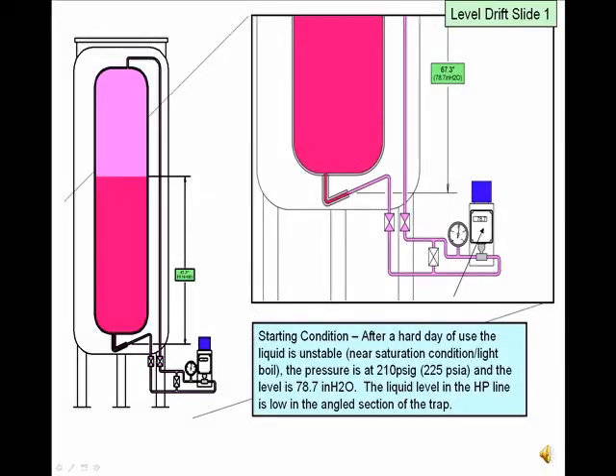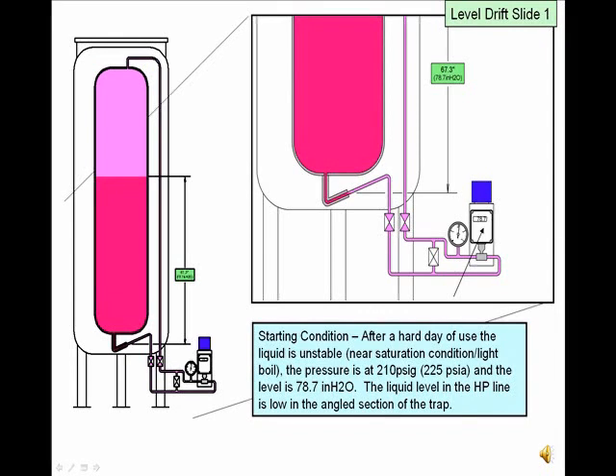For the following example, the tank has seen heavy use during the day and is at 210 PSI gauge pressure. Heavy usage, and sometimes normal usage, can result in a tank without sub-cool, meaning the liquid in the tank is in a light boiling mode. By the nature of heavy or normal usage, the liquid in the high pressure line will be toward the bottom of the trap. In this example, the differential pressure gauge is indicating 78.7 inches of water.